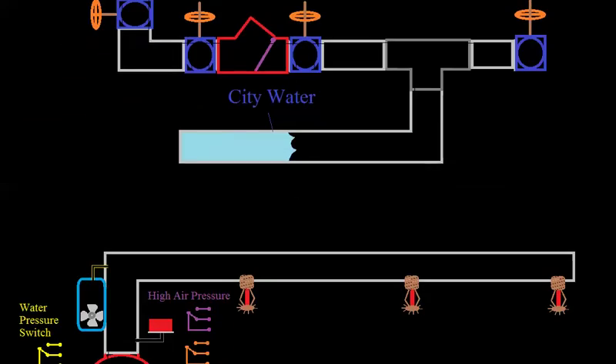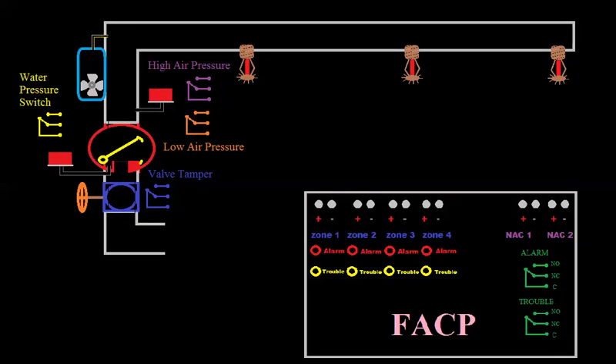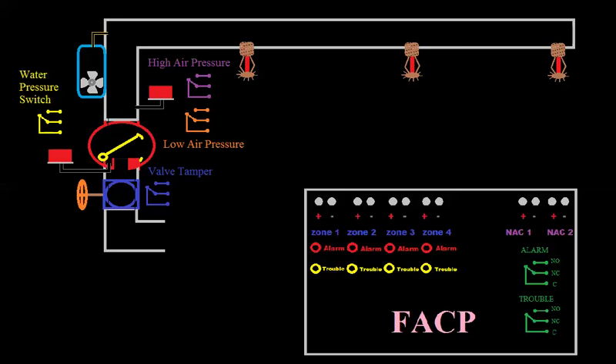When your system loses pressure, you want to know, but it's not an alarm — it's not really an emergency. So you're either going to make that a supervisory switch like we did with our valve tampers, or if your panel doesn't have that capability, it's going to be a trouble. The purple and orange contacts drawn here are both on the air switch — you have high air pressure and low air pressure. The water pressure switch is like your water flow alarm in a wet system, so that's going to be an alarm. The valve tamper: if you don't have supervisory it's going to be trouble; if you do, that's what it'll be. Anything that could shut off the water and compromise the system's functionality, you have to monitor that.